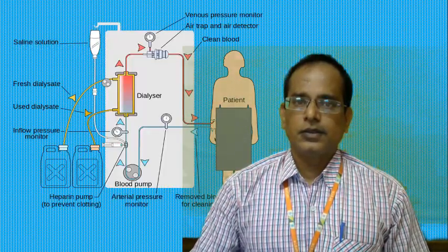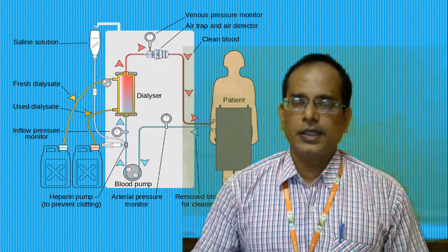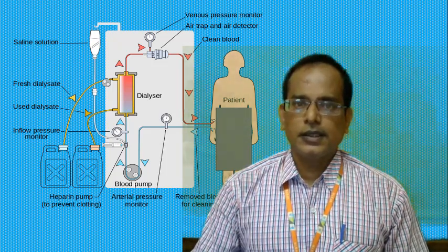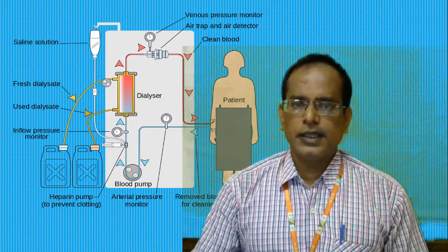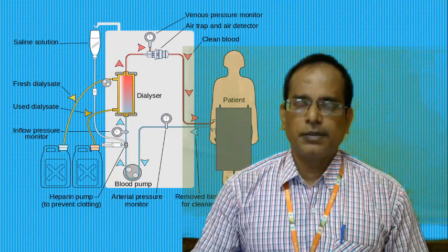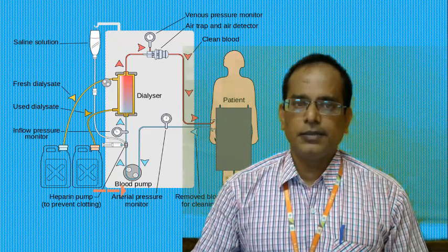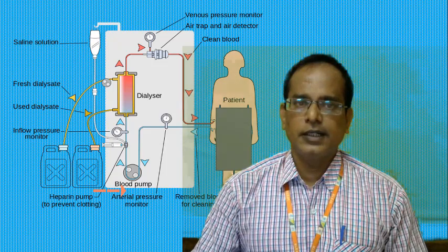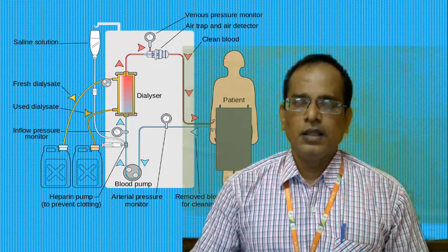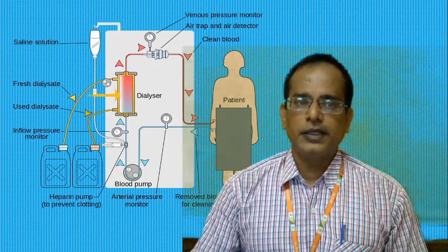Here you are seeing a hemodialyser. Unclean blood is taken from an artery and given to a peristaltic blood pump, which pumps this unclean blood to the dialyser.